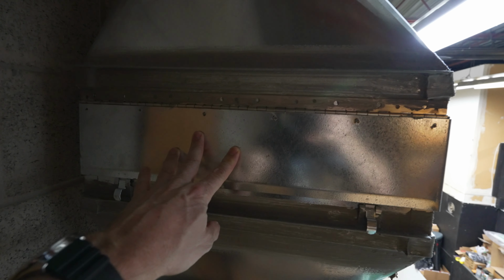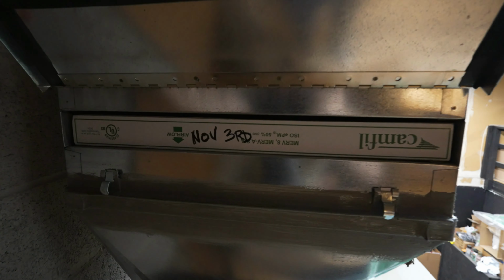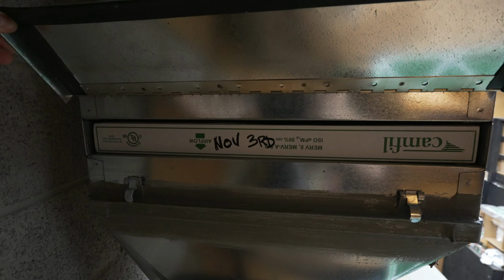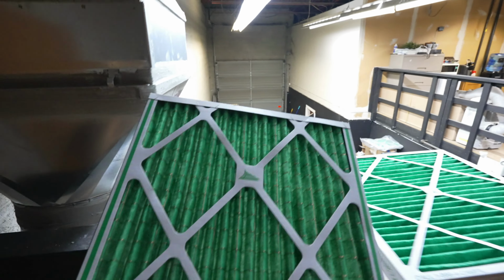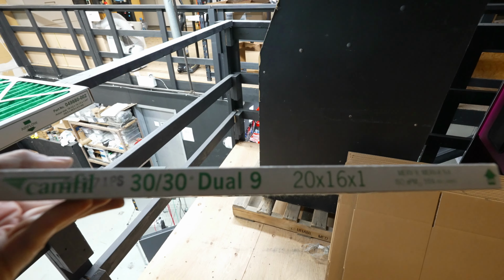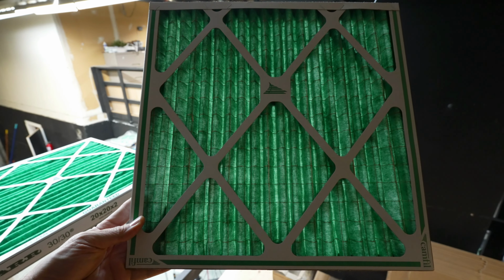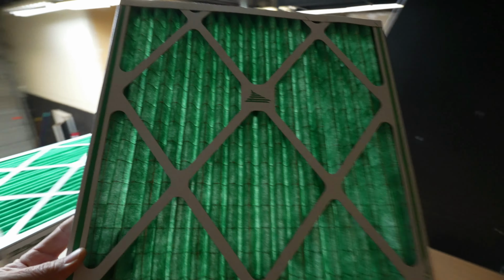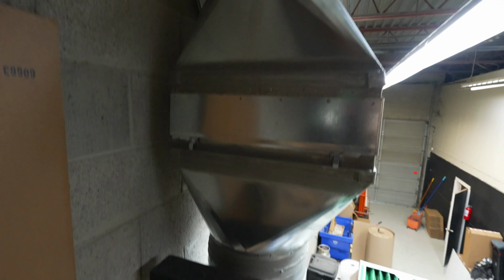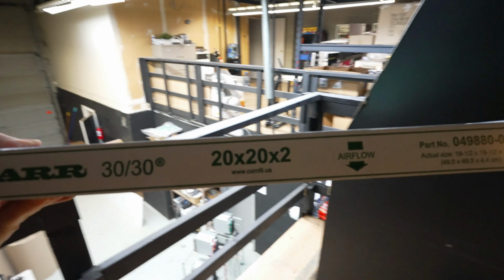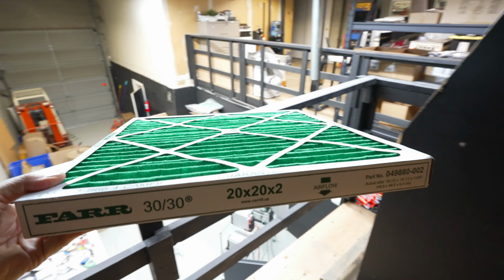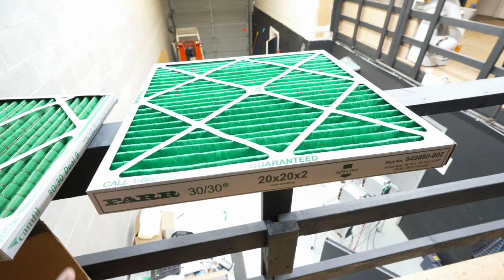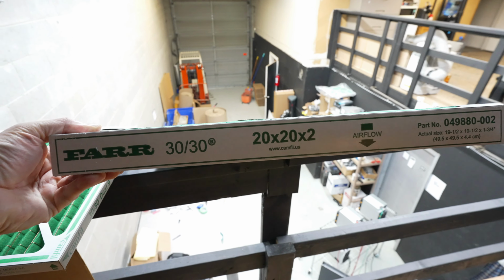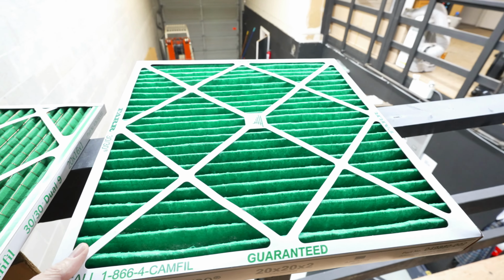Here's the fresh air intake, or filter box, and this is where the first real major mistake was made. Originally we were recommended a much smaller filter box that housed 20 by 16 by 1 filters. These lasted all of about 2 days before completely plugging up. The company had to come back, remove the whole unit, and custom build a system to house 20 by 20 by 2 filters. Ever since we put these in, we've never had any issues whatsoever. This is exactly what we use at the other mining facility, and we've had zero issues there as well.